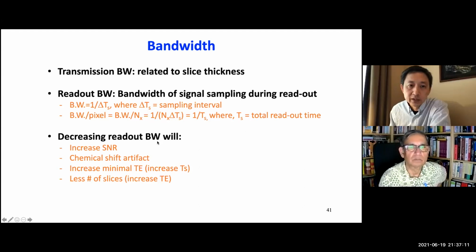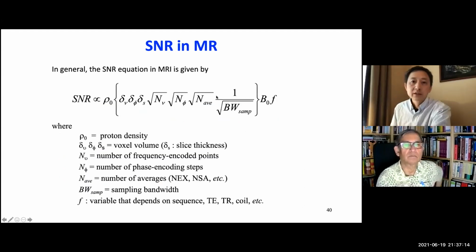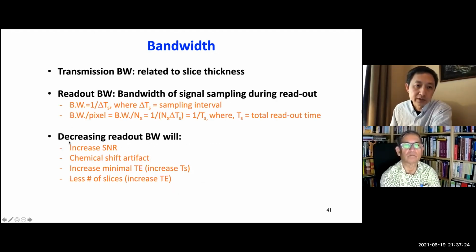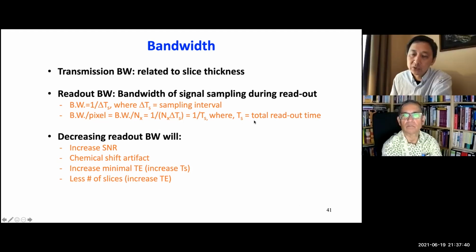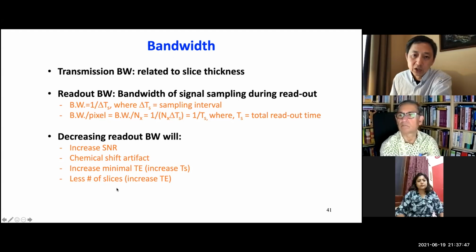Like I mentioned, one way to increase SNR is to use a smaller bandwidth, so it is desirable to use a lower bandwidth. But what else will it cause if we reduce bandwidth? Reducing bandwidth increases SNR, that's good. But if there's a chemical shift artifact, that will enhance the chemical shift artifact. It will increase the minimum TE because the readout time increases. That's not good for a T1 weighted image. Also, because the total readout time is increased, the number of slices will be less, so slice coverage will be less. So we have to understand those.